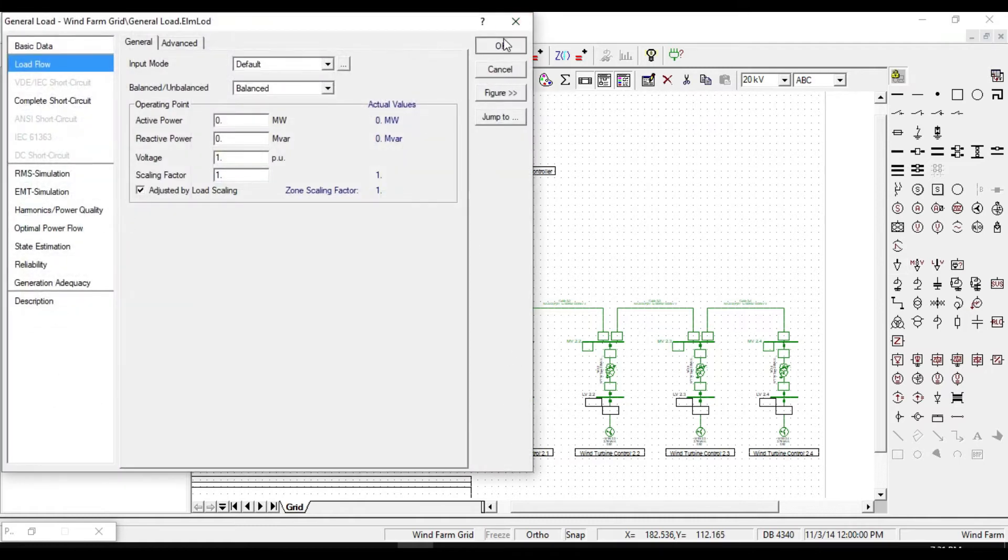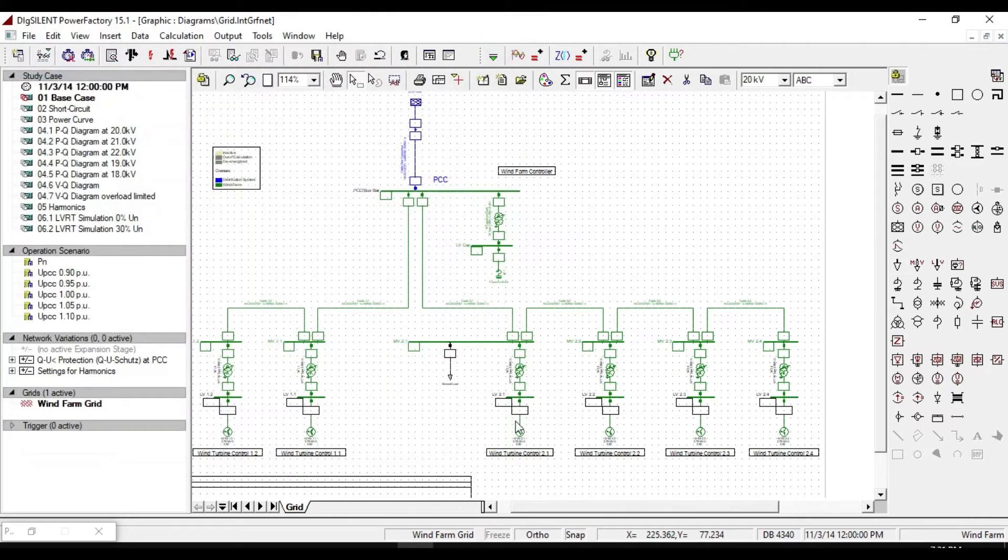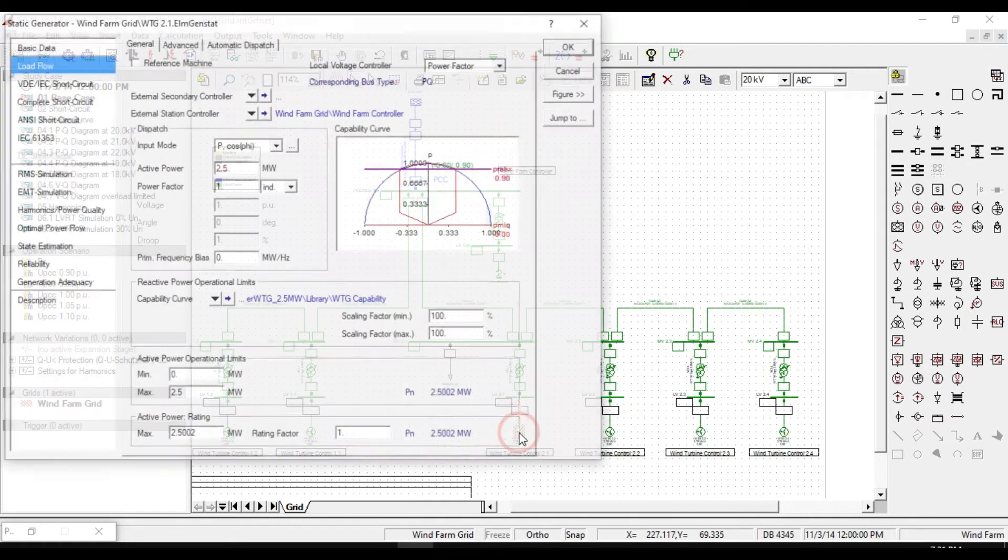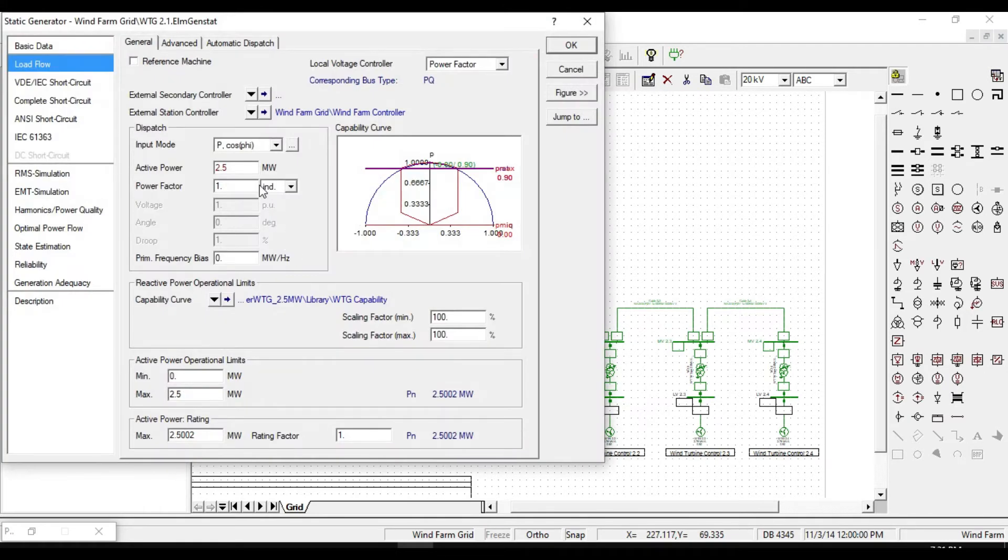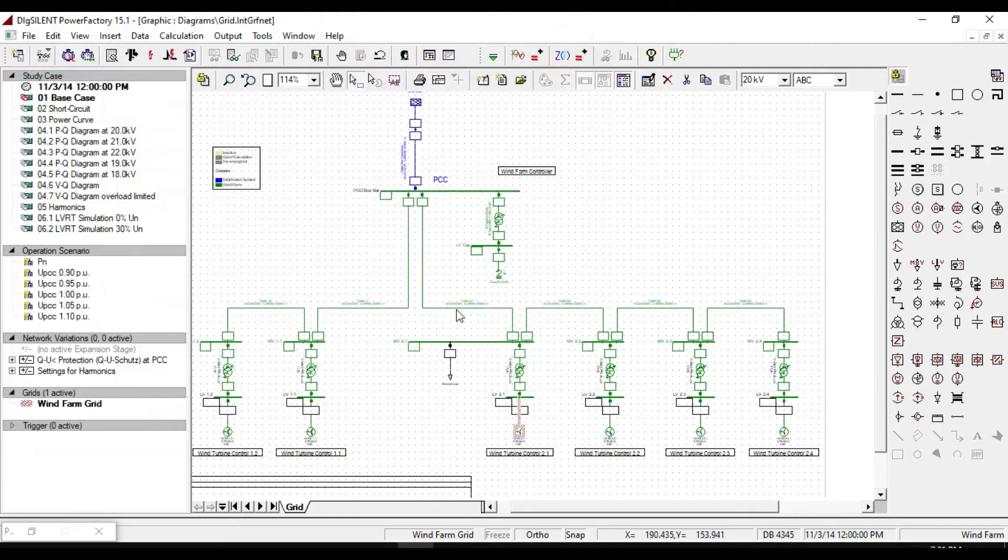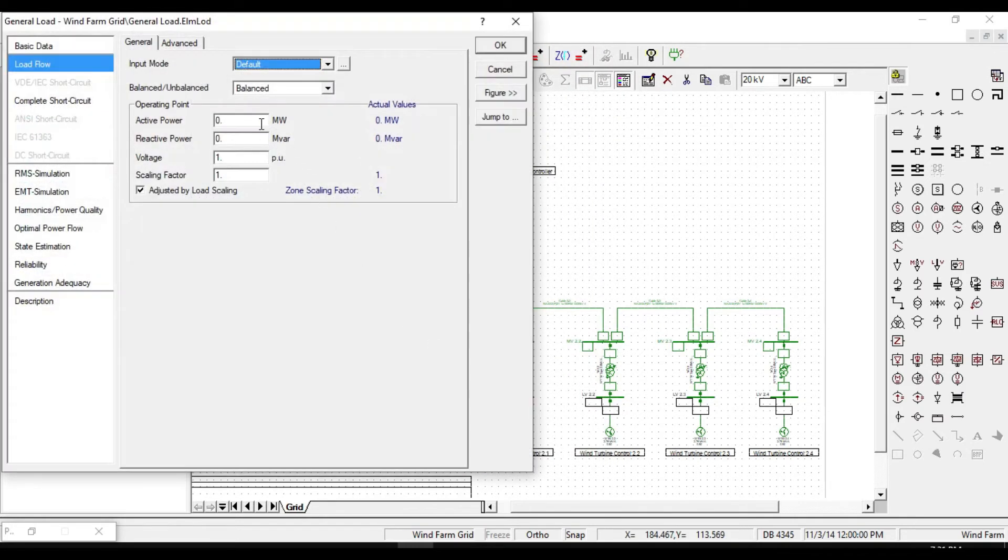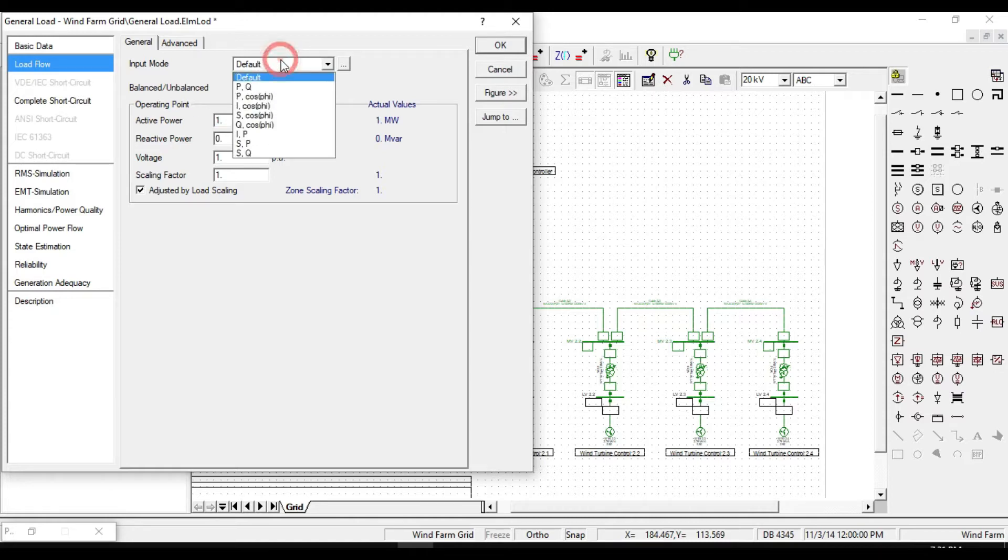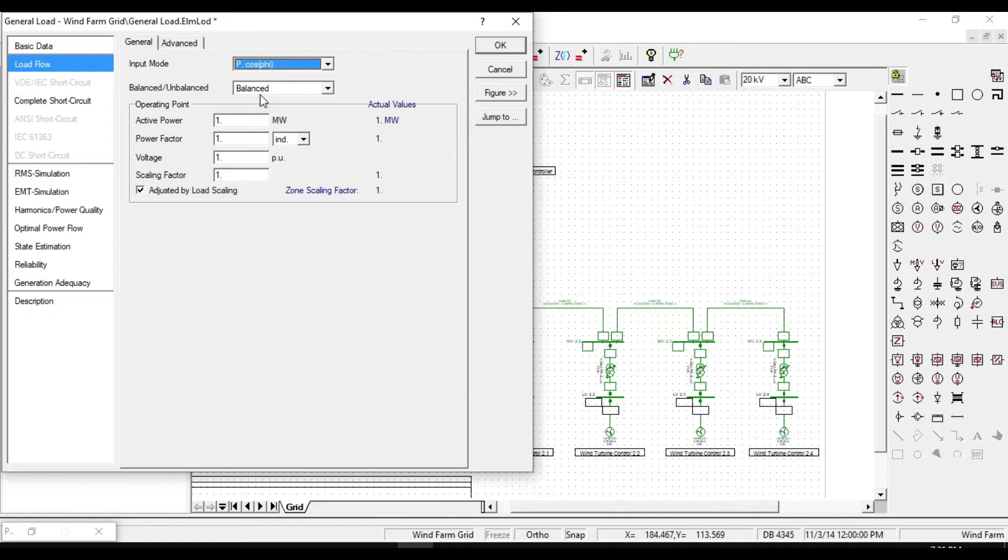If we look at the power rating of this generator, we can see that it produces 2.5 megawatt active power. Assume 1 megawatt active power for our general load, and change input mode to P cos phi and enter 0.9 for power factor.